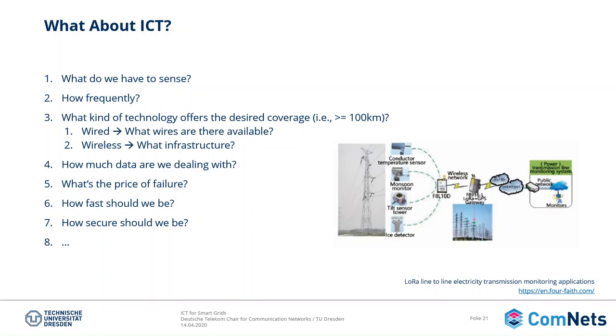In the standards, for example, the time between detecting a short circuit fault and isolating this part of the grid that has the fault must be no more than 30 milliseconds. That means you need to sense the fault, send the information back to the central processor or the cloud or your application, detect the fault, and send back the command to isolate the network — all within less than 30 milliseconds. This needs extremely fast communication.